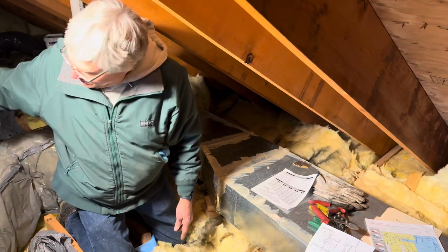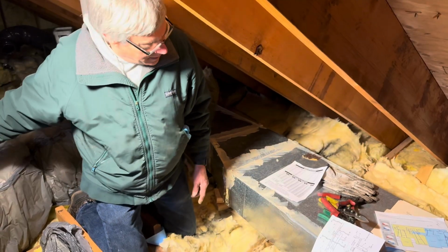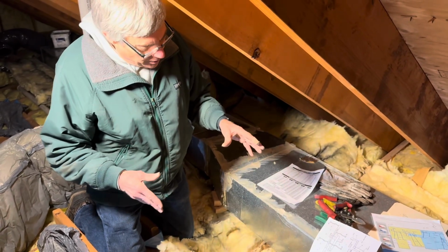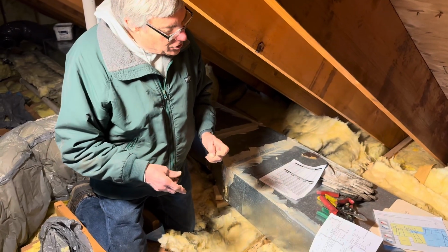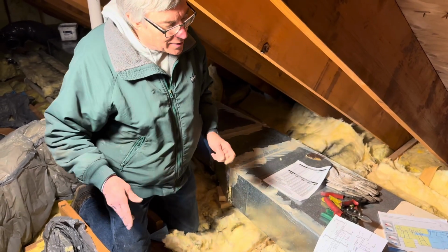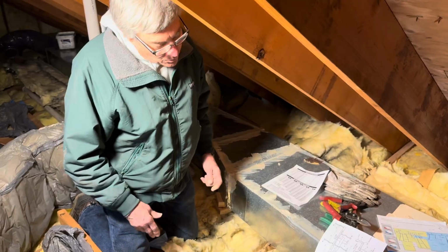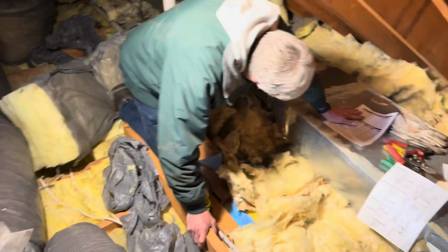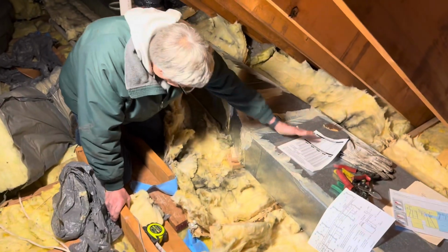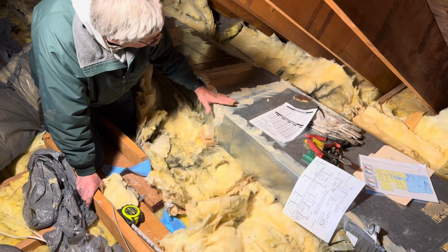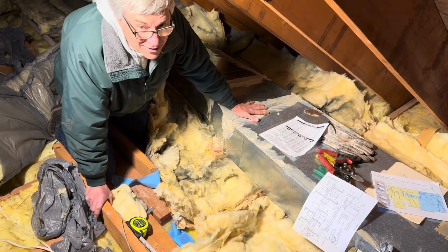And at the very end, we're going to supply another duct because we're going to change the design of where this supplies things to, because it wasn't laid out very good to begin with. So now we have the transition, and we can see that at every transition, this has already been sealed with a lot of gooey mastic, but we no longer have any air leakage.